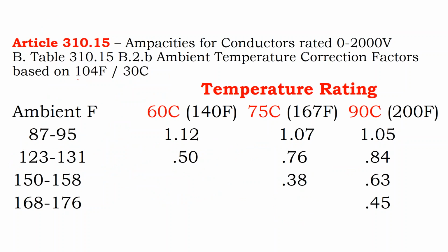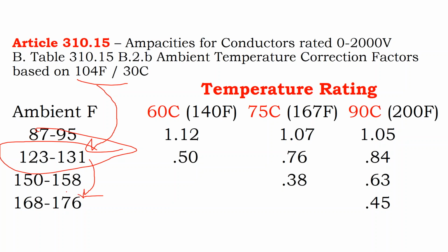And so the way that this chart would work is you might be doing your calculations based on 104 degree ambient temperature for getting your ampacity ratings, and you'd be looking at all these charts in code that are applicable to 104 degree ambient ratings, but you say, well, wait a minute, up on my rooftop, it's not 104 degrees. Let me clear out this wiring here. Up on my rooftop, it's not 104 degrees. I go to PV watts in the summer day, the hourly data, and I see when it's 104 degrees outside, it might be 130 or more up on my rooftop. And then if my cables are dangling within 1 inch of the rooftop, now I have to go and design up in this 176 or maybe even more. I might knock myself out, there might not be any cable out there that's good for my temperature rating.